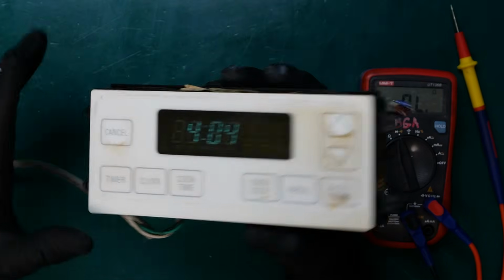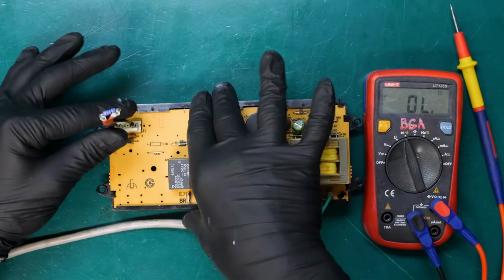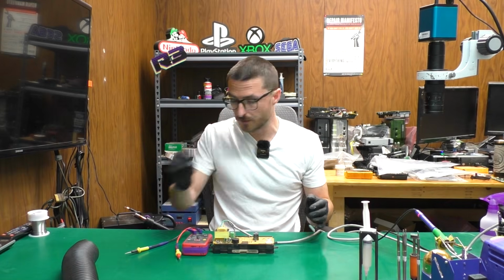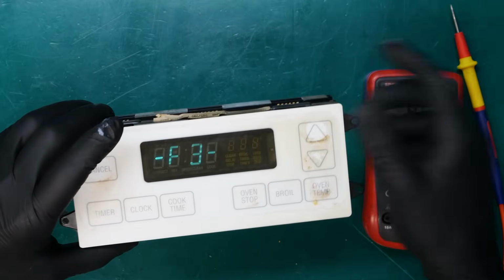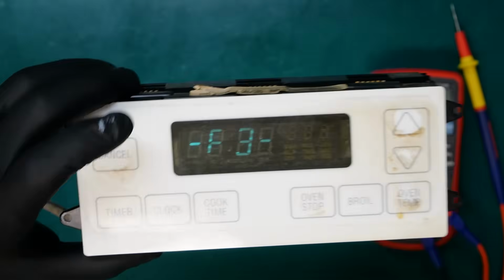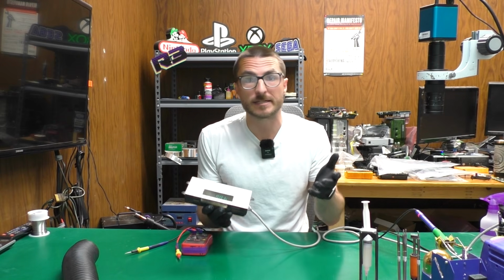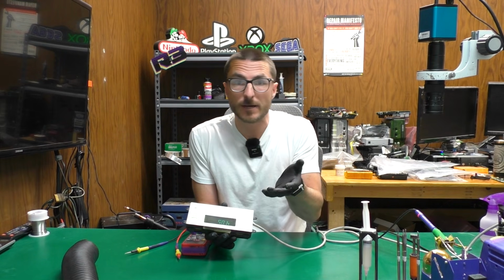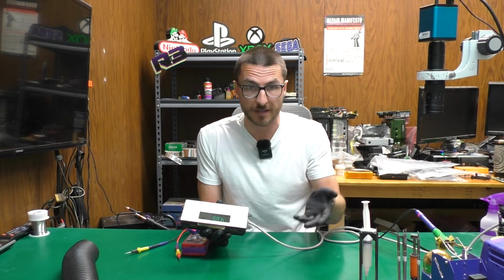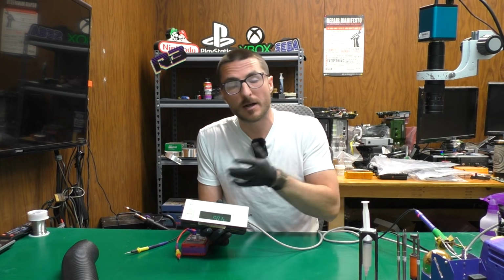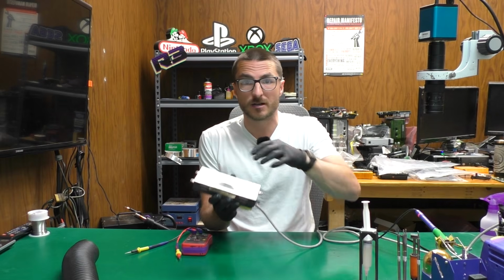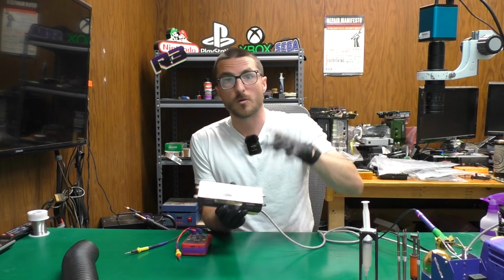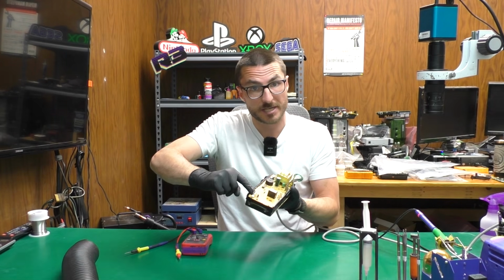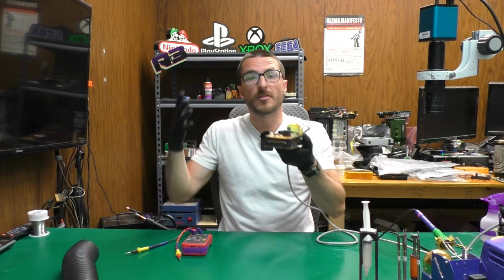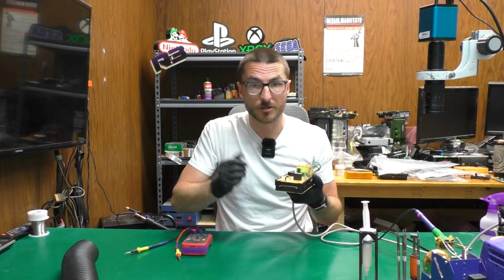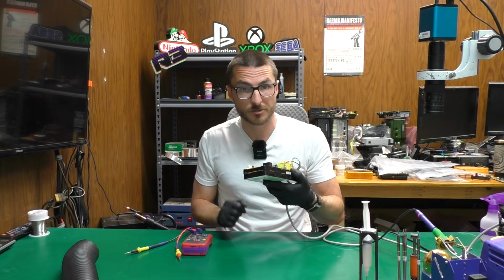Okay, let's cancel. Next, I'm going to remove this sensor I installed, which mimics the temperature probe. And we're going to try again. And sure enough, we have our F3. An F3 error code indicates an issue with the temperature sensor. Now, it is possible for the temperature sensor to actually have failed and be defective. However, it is more common for there to be an issue between the communication of the controller and the temperature sensor. What I mean by that is there are connections here where the sensor plugs into that can fail and cause that error code to trigger. So let's open up the unit and take a closer look.